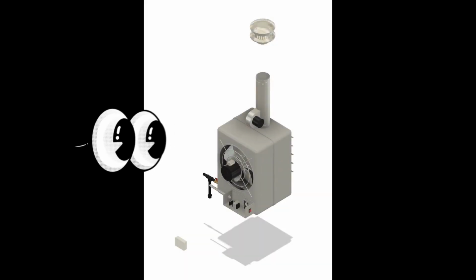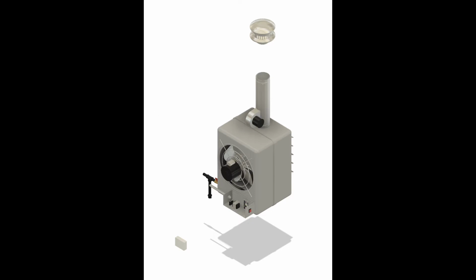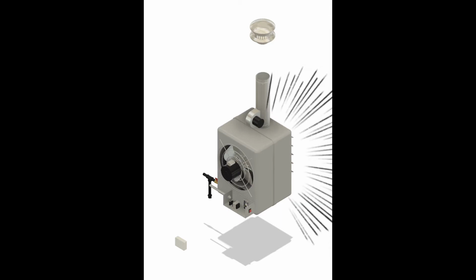If you look at the back side, you can see there'd be a rain cap up on the roof. Then there's usually some sort of electrical control box. I took the cover off in this illustration so you can see better. And you can see there's a fan on the back side that blows the ambient room air across the heat exchanger inside the unit heater, and you get warm air coming out the front of the unit heater.